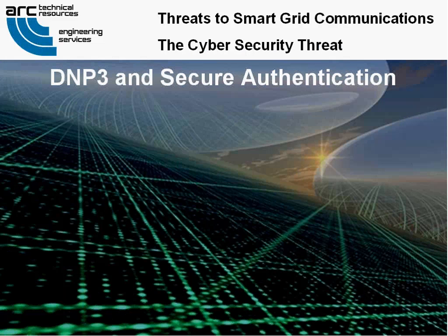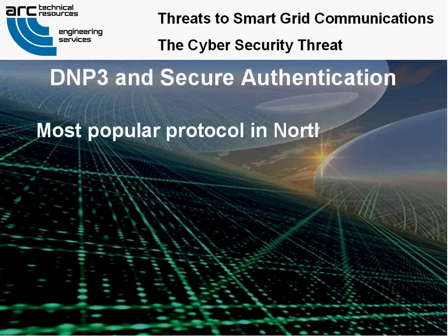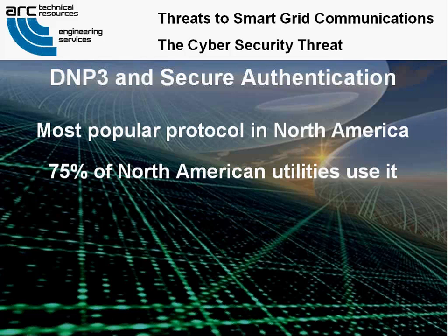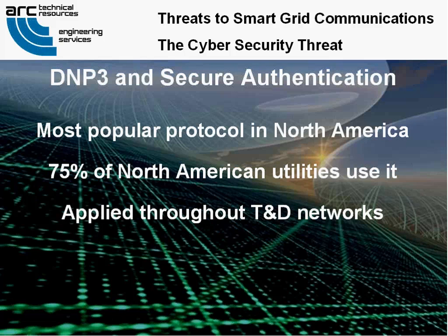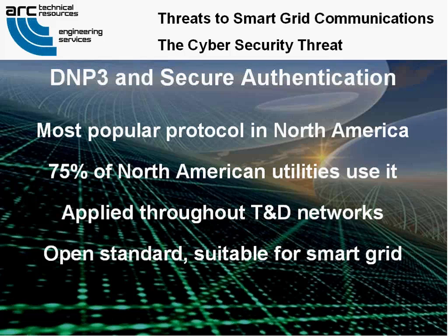The Distributed Network Protocol, known as DNP3, is the most popular utility automation protocol in North America. Over 75% of North American utilities were already using or planning to use DNP3 in their SCADA networks. It is applied throughout transmission and distribution networks, providing connections from master stations to substations, between devices within substations, and out to pole-top devices along the feeders. DNP3 is an open standard, and therefore is a good candidate for the smart grid. Unlike the more advanced IEC 61850 protocol, it does not provide structured naming and complex object models.